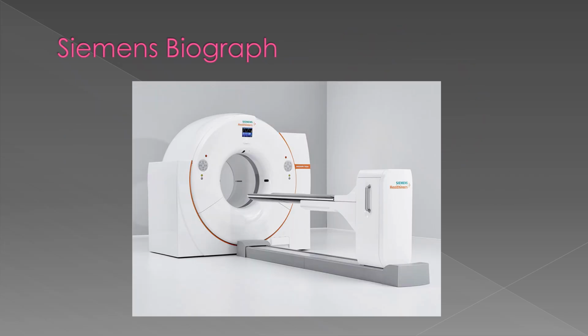This is Siemens Biograph. So I'm going to show you a couple different types of PET scanners. The Siemens ones all kind of look the same. They're slightly different. Over here, you have a manual release for the table bed. The table moves on this track down here. You don't really want to pile things or step on that. If you step on it, you could break it. Same thing, I guess, if you're piling heavy things on it. Technologists always have a tendency to put the leg thing down there, but really you shouldn't. There are moving tracks underneath of here, and it's very important that you don't damage those or the table won't move in and out.